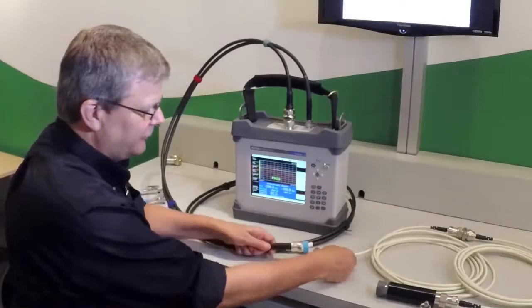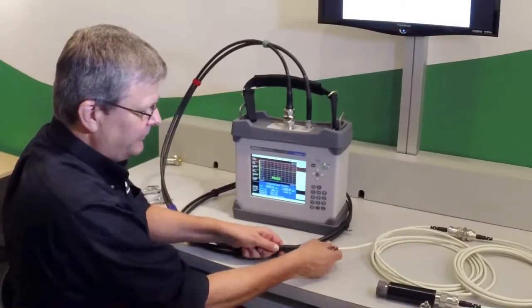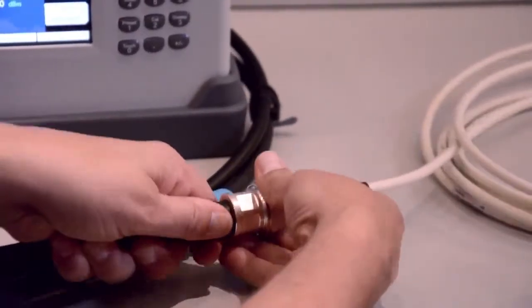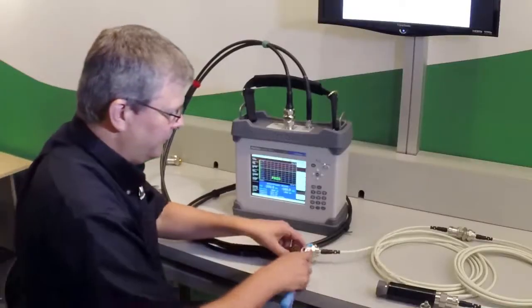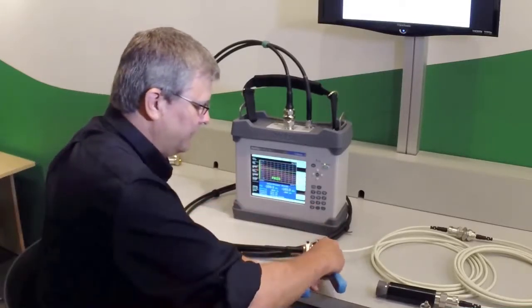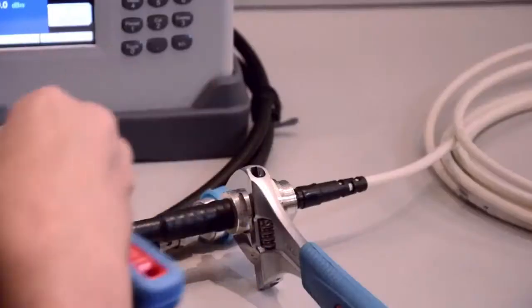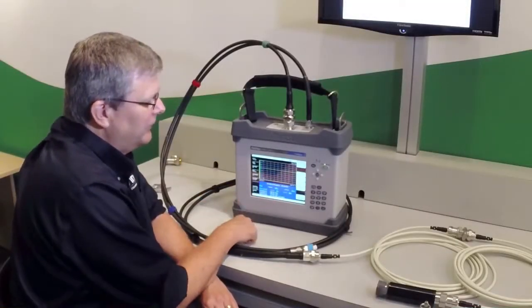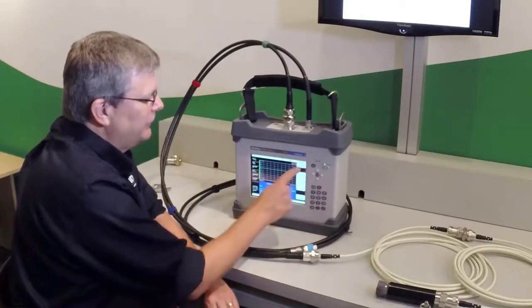Now I'm going to connect the system under test to the PIM test port, and here it is important that we apply the proper torque so that we maintain low PIM at the test port connection. We're now ready to proceed to performing our first PIM measurement of this system.